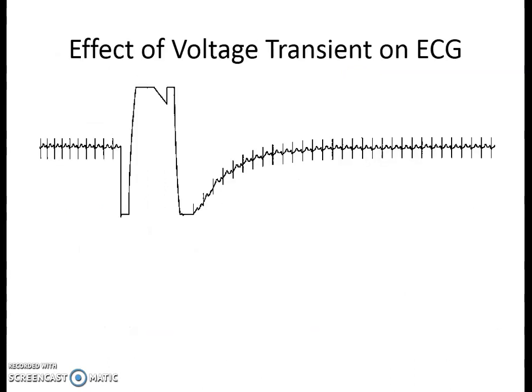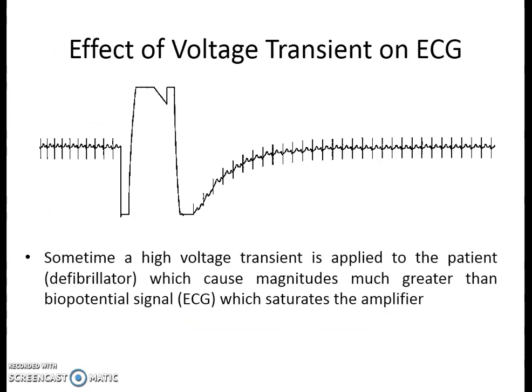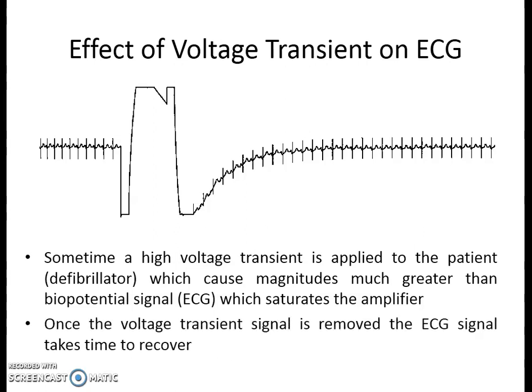This is one of the effects of a voltage transient on the ECG machine. Sometimes a high voltage transient is applied to the patient — such as from a defibrillator — which causes a magnitude much greater than the biopotential signal, and this saturates the amplifier. Once the voltage transient signal is removed, the ECG signal takes time to recover. This is the same thing you can see in the diagram: this is the voltage transient and this is the time of recovery.